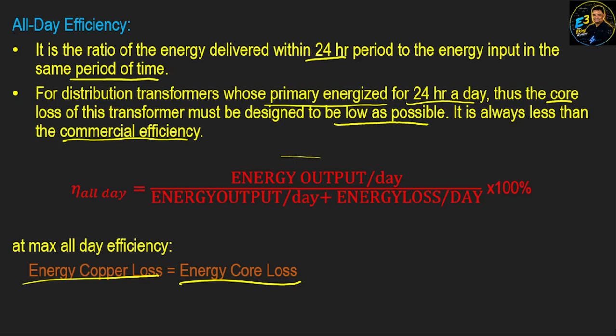Okay, now let's try to use this formula on an example. A 25 kVA distribution transformer has the following losses: core loss 300 watts constant and full load copper loss 600 watts. The transformer operates on the following load cycle: 6 hours at full load, 10 hours at half load, and 8 hours at no load.